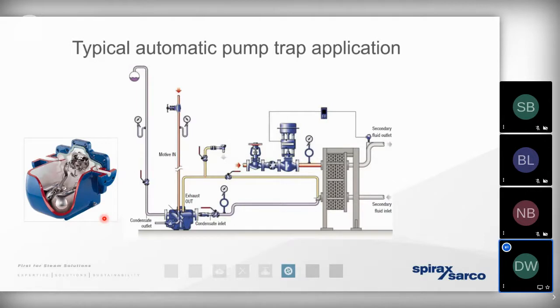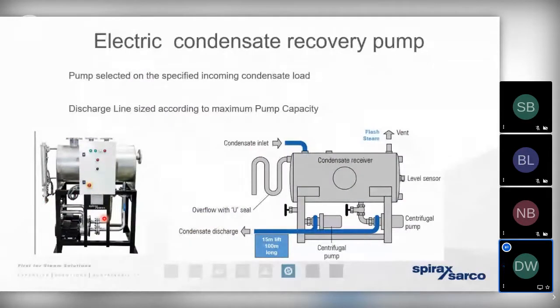We're enabling the heat energy to pass across the heat exchanger very, very quickly without the risk of stall occurring. And we're able to get that condensate back to the boiler house where that high heat content can be used quickly and efficiently. But of course, we know that there are always going to be occasions where we need to add a significant amount of motive energy to a large mass of condensate. For example, if we're moving condensate from the very, very far part of a large site. And we can do that in a number of different ways.